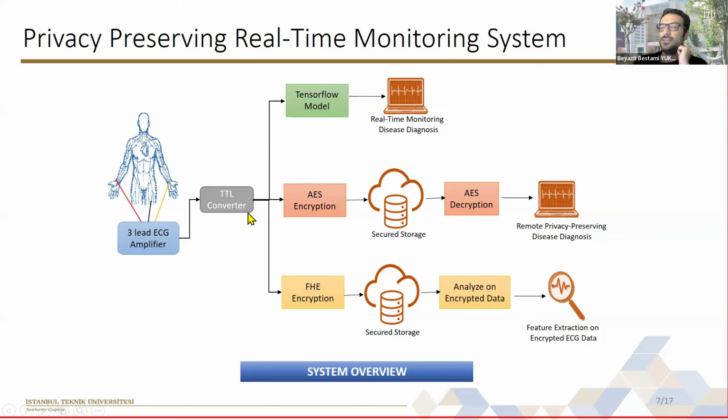Next, the serial connection, which transmits the amplified electrical signals, now converted into digital data, from the preamplifier to the computer, and it uses standard protocols like RS-232 or USB. Here, speed and reliability are the key because the data needs to be processed in real time, and this is especially critical in emergencies where every second counts.